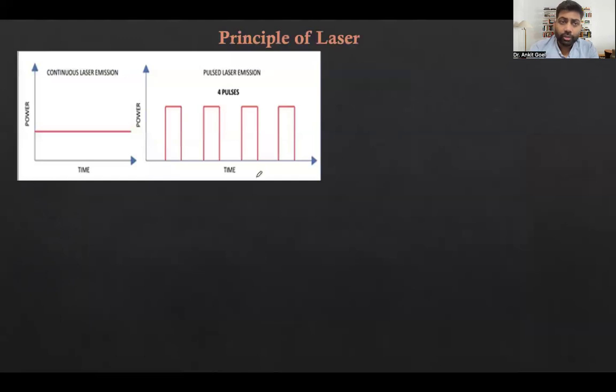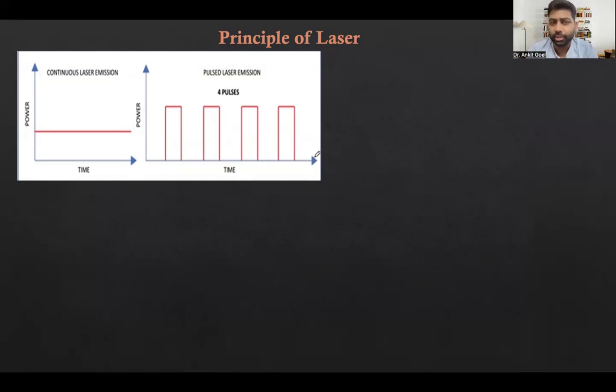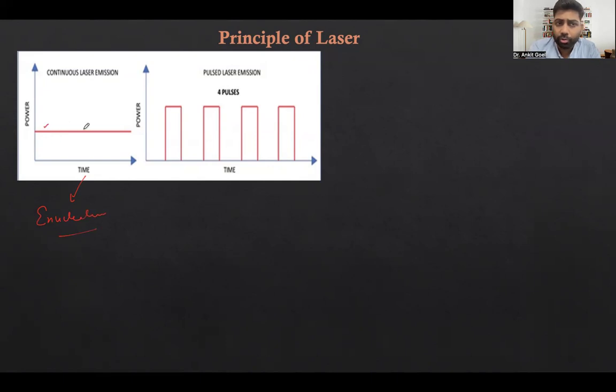There are two basic ways laser energy can be released: continuous emission and pulsed emission. Continuous emission is required when performing enucleation of the prostate, where laser energy is activated throughout the procedure. Pulsed emission is required when performing lithotripsy. So the most common urological application of continuous emission is enucleation of the prostate, and pulsed emission is most commonly used for lithotripsy.